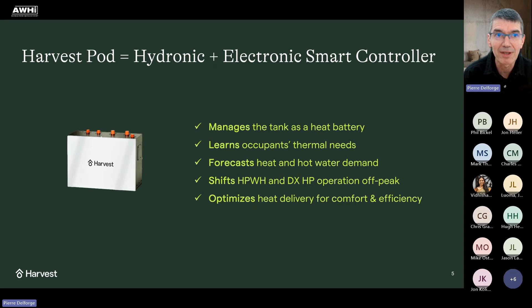The pod also controls delivery, and that's really important because in order to achieve a high storage capacity in the system, we use a low return temperature. So we have a high temperature delta across the delivery system, typically around 70 degrees Fahrenheit, which means that with 120 gallons of hot water and a 70-degree delta T, we are able to achieve up to about 75,000 BTUs of storage. And I have a slide to talk a little more about this later, but that's really a key differentiator, because that's necessary to be able to shift not just domestic hot water, but also space heating loads.